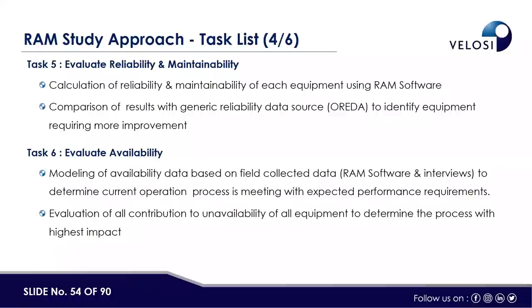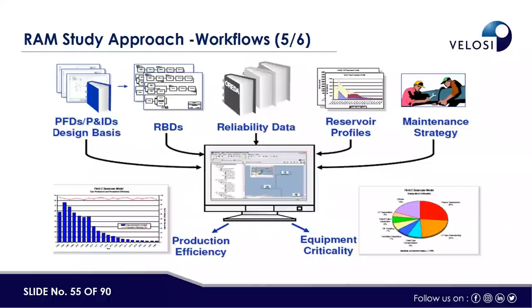Task five is evaluating reliability and maintainability — calculating the reliability and maintainability of each equipment using RAM software or in-house Excel sheets. Results are compared with OREDA to identify equipment requiring improvement. Task six evaluates availability — modeling availability data based on field-collected or client-provided data to determine if the current operational process meets expected performance requirements. We also evaluate the contribution to unavailability of all equipment to determine which process has the highest impact on production losses.